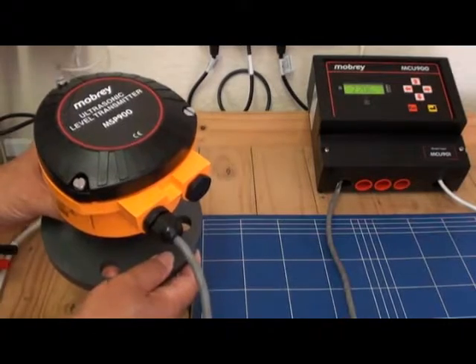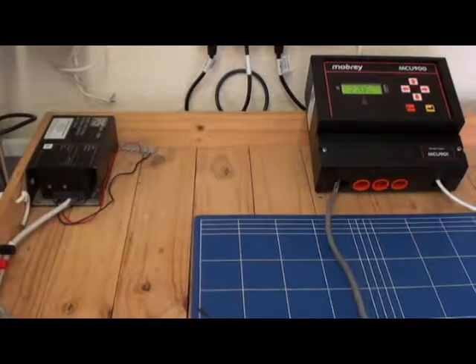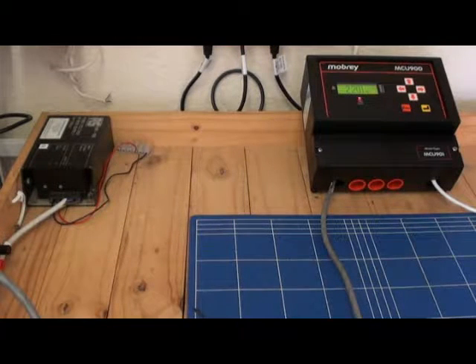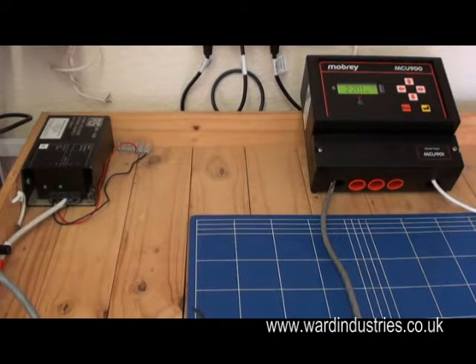If powering the transmitter from any other supply though, it is the responsibility of the user to ensure that a suitable intrinsically safe barrier is fitted in the safe area.